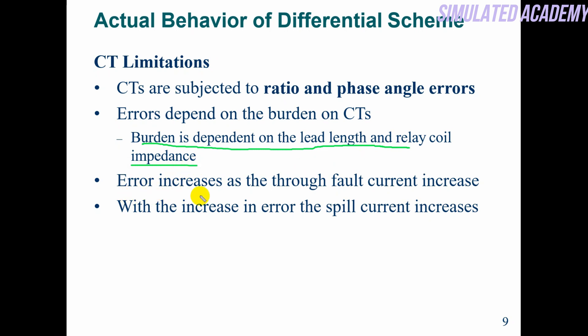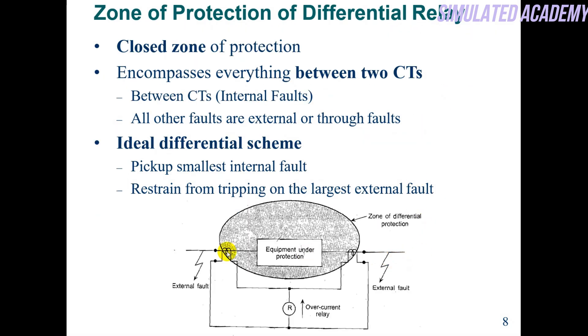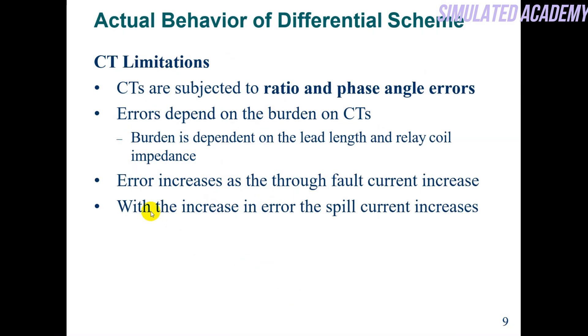Error increases as the through fault increases. When the through fault current value increases, and because of differing turns ratios, as the current value keeps increasing, the mismatch increases. That mismatch current will pass through the relay, causing it to operate. So when the through current increases, the relay may operate incorrectly.